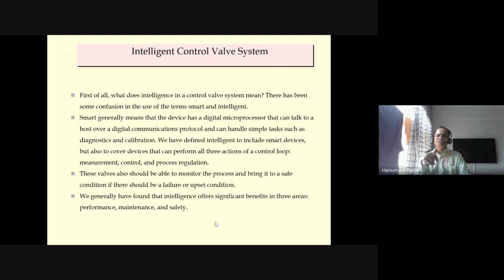Means smart means simple tasks such as diagnostics and calibration, which we get using the HART protocol. But intelligent means it will measure, it will control, and regulate also. So it acts as a controller. That means intelligent. These should also be able to monitor the process and bring it to a safe condition if there is a failure or upset condition. So an intelligent control valve, as it has a control facility, can safely shut down the valve.